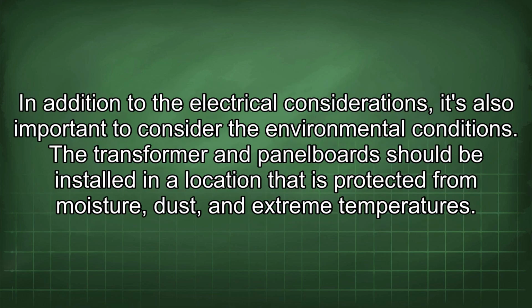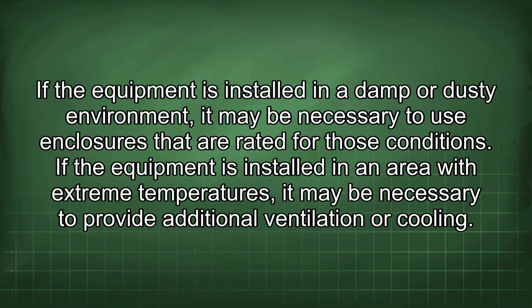In addition to the electrical considerations, it's also important to consider the environmental conditions. The transformer and panel board should be installed in a location that is protected from moisture, dust, and extreme temperatures. If the equipment is installed in a damp or dusty environment, it may be necessary to use enclosures that are rated for those conditions. If the equipment is installed in an area with extreme temperatures, it may be necessary to provide additional ventilation or cooling.